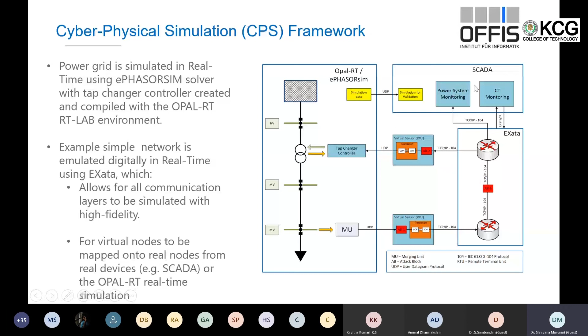So again, a very simple network, through a tap change transformer connected to a load and to a larger part of the grid, was made in OPAL-RT software, and it is interfacing with the EXATA software. It's the same here. The entire tap change transformer model is kept in the OPAL-RT simulator, and you have a virtual controller also. It has its own virtual IED, or virtual sensor, and that is what interfaces with the EXATA software. And you have the rest of the SCADA, which is emulating the SCADA system sitting here.